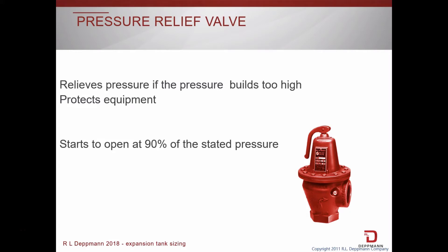Relieving this excess pressure protects the equipment in the system as well as the people in the building. What we're talking about is hydronic relief valves today, which are not like plumbing relief valves. A plumbing valve will pop open when its setting is reached. Hydronic relief valves will actually start to weep at about 10% less than the set point. So a 50-pound valve starts to open at 45 psi.